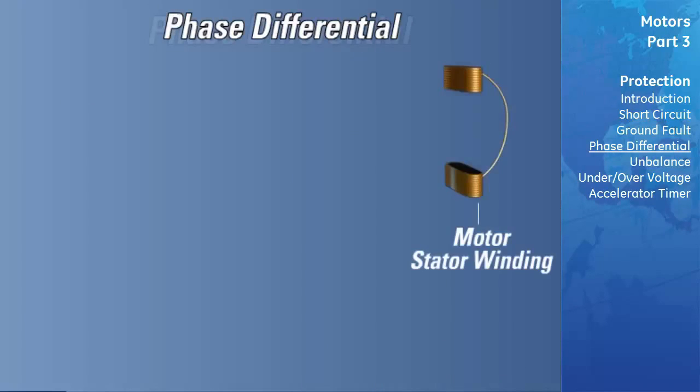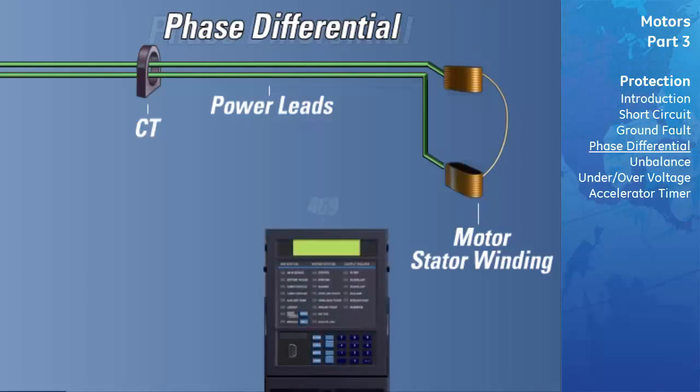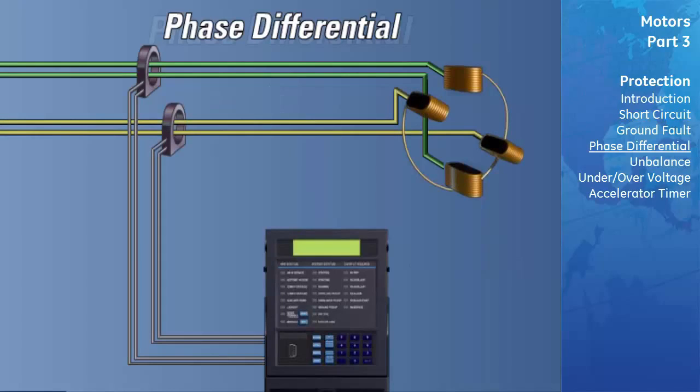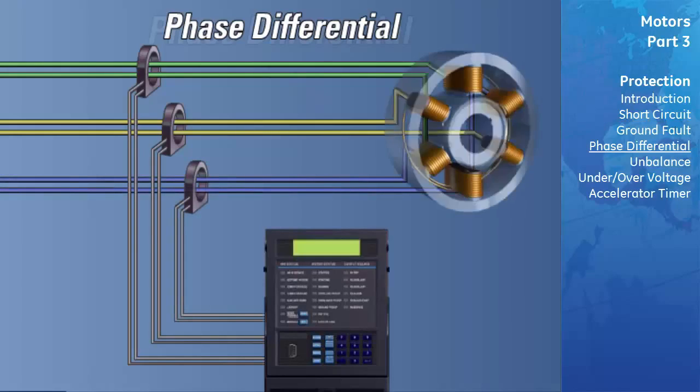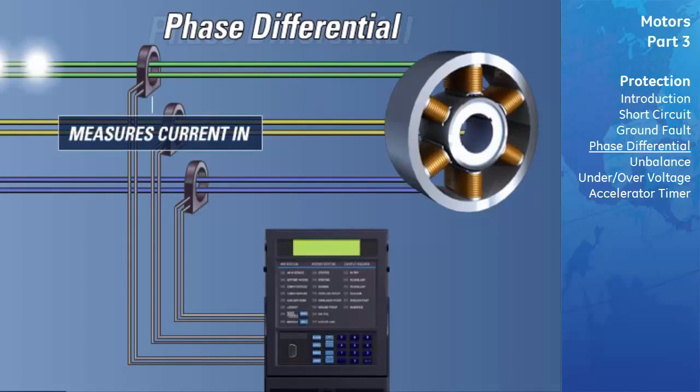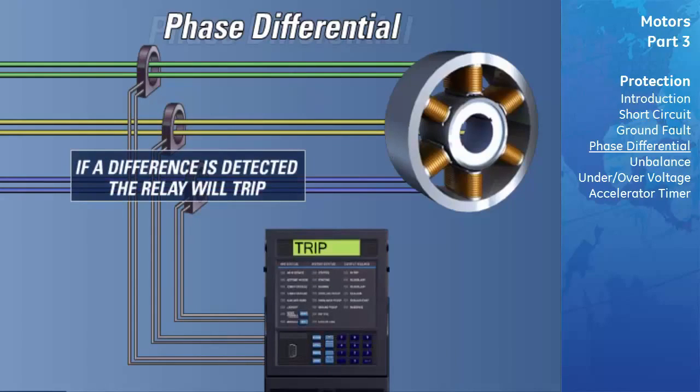Phase Differential Current Protection. This feature consists of three instantaneous overcurrent elements for phase differential protection. The differential trip element function can only be used if both sides of each stator phase are brought out of the motor for external connection, such that the phase current going into and out of each phase can be measured. The differential element subtracts the current coming out of each phase from the current going into each phase and compares the result or difference with the differential pickup level. If this difference is equal to or greater than the pickup level for a period of time greater than a user-specified delay, a trip will occur.